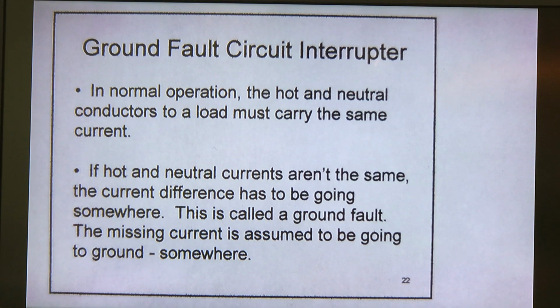If the hot and neutral currents aren't the same, well, the current has to be going somewhere. We don't know where maybe, but we know that it's not behaving the way it should. And this situation is called a ground fault. So the missing current is assumed to go to ground somehow, somewhere. We don't know, but we do know that there's an imbalance, and that's usually a dangerous situation.